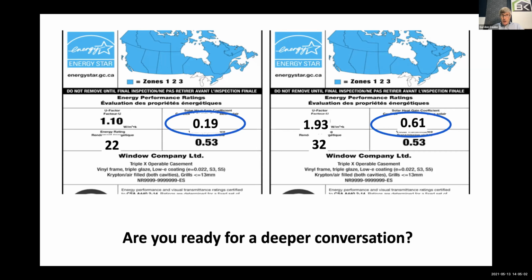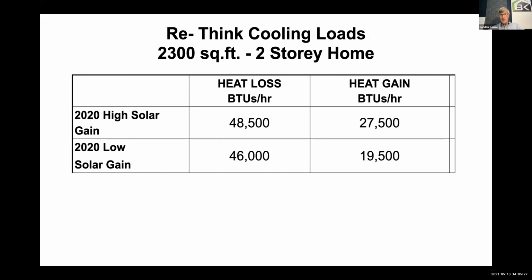And I just don't want you throwing more tonnage at this because remember, that's an instantaneous load. That load is only there for a short period of the day. So you have this odd circumstance. You're going to oversize for maybe a few hours out of the day, and that's going to mean the rest of the day it's not dehumidifying correctly. So we have to find a way to do this, and you can do it partly by choosing better glass, or you're going to find different heating cooling sources. Is what you want to get to.